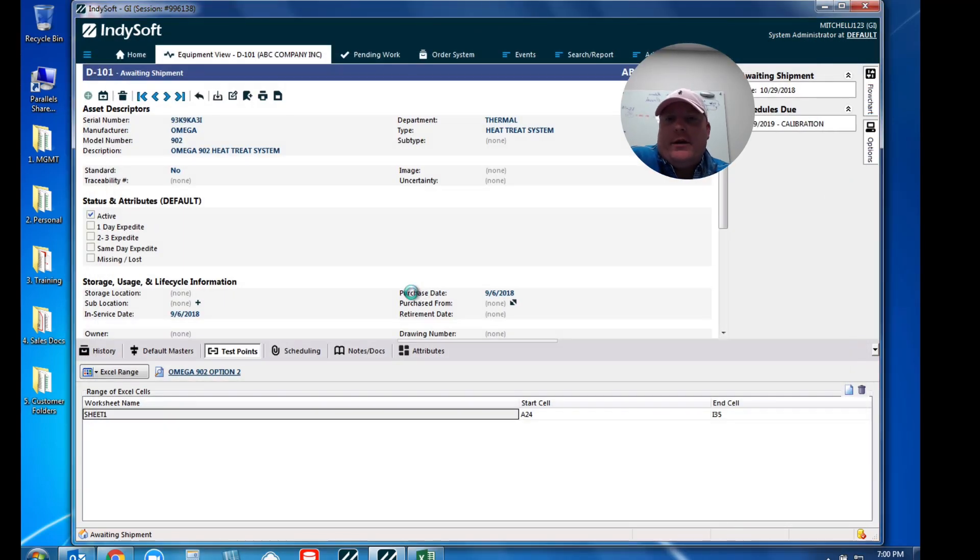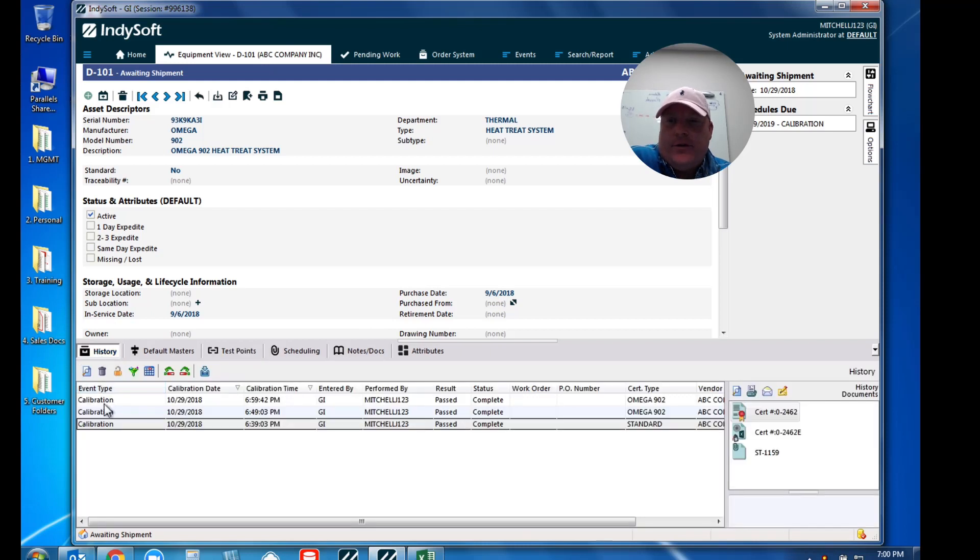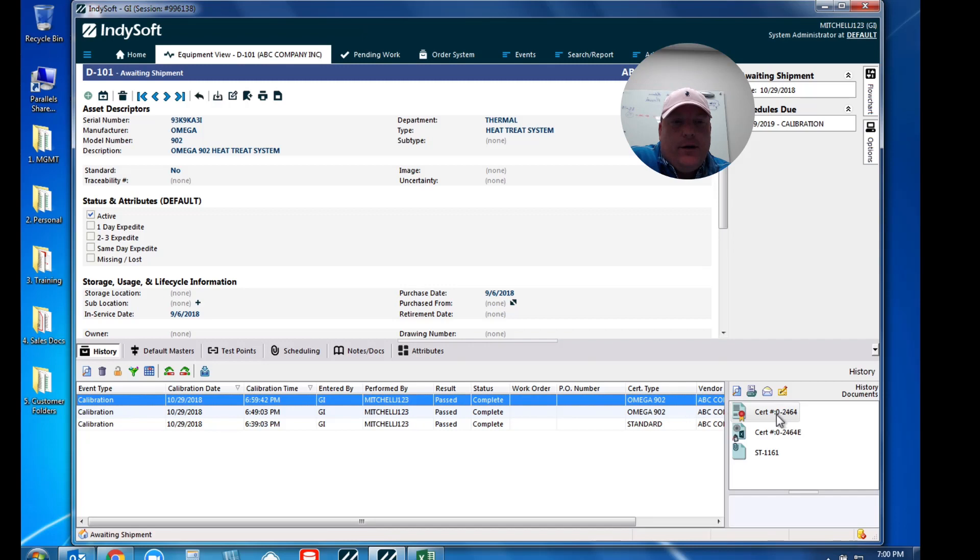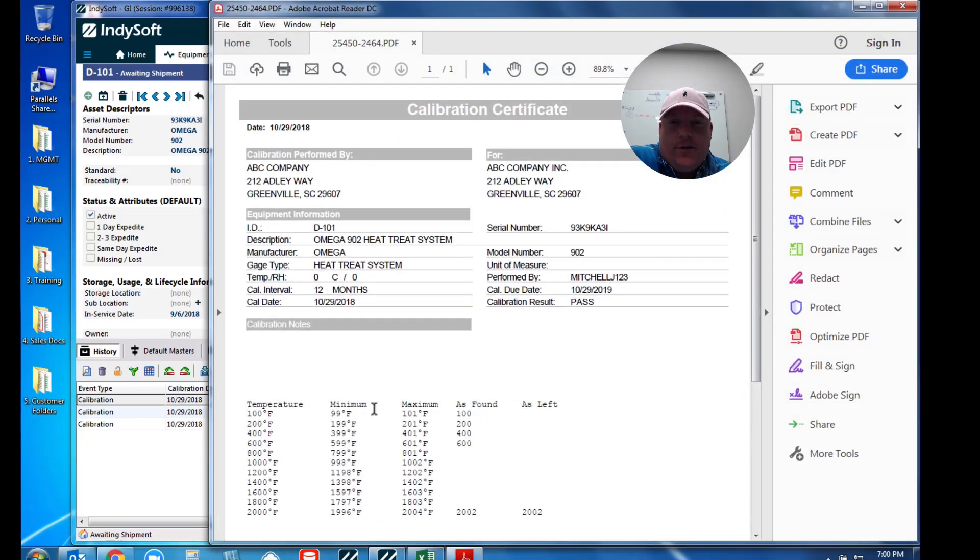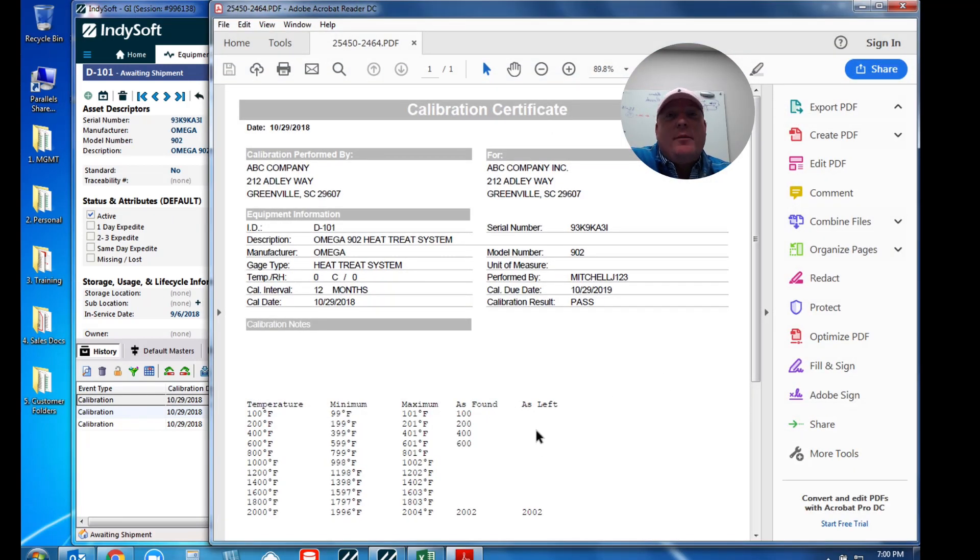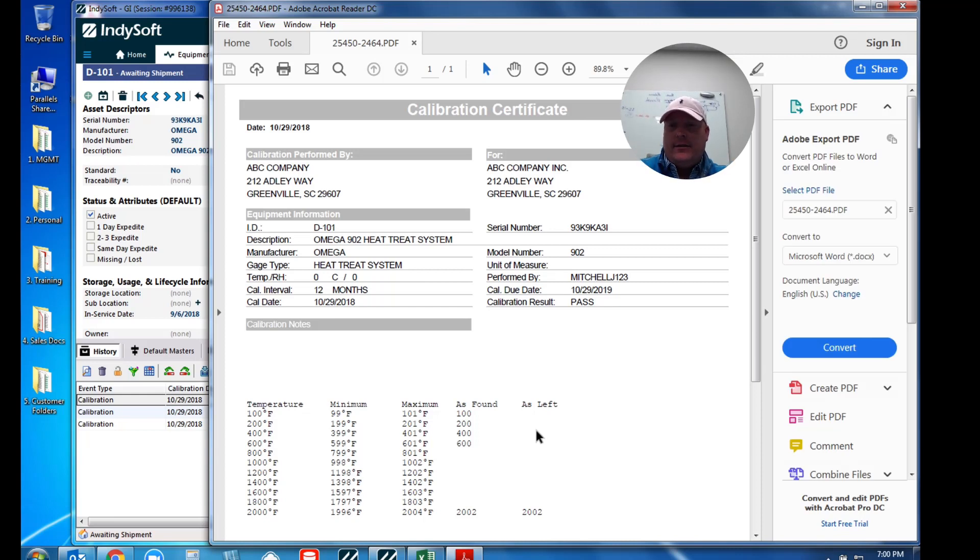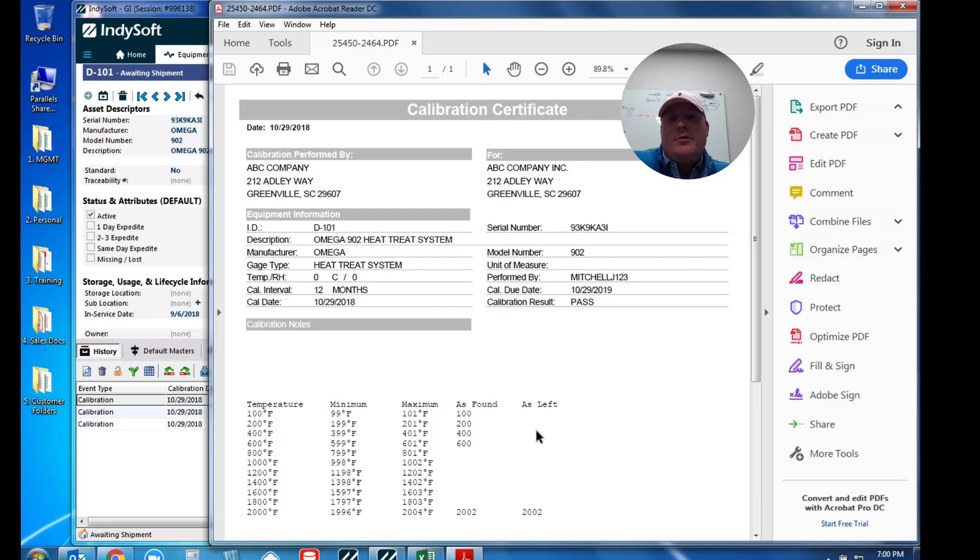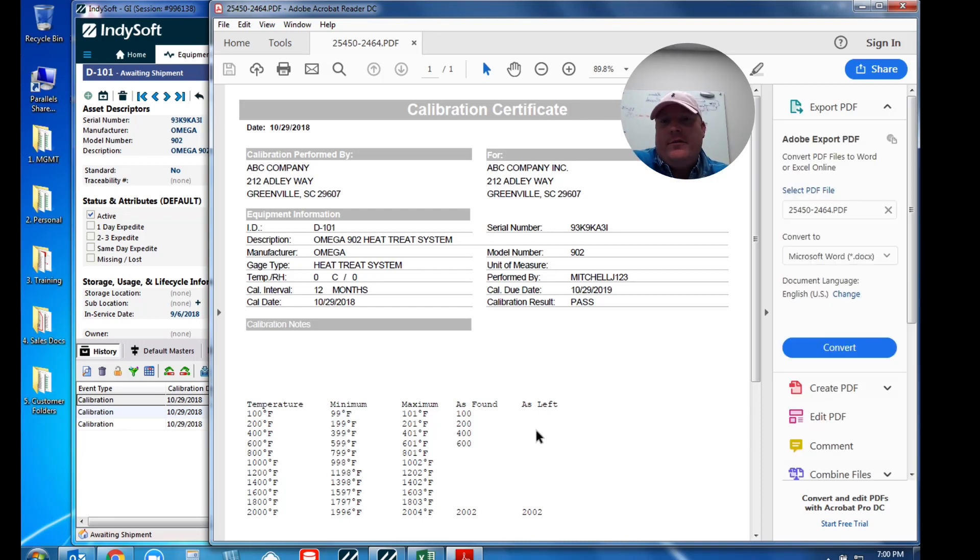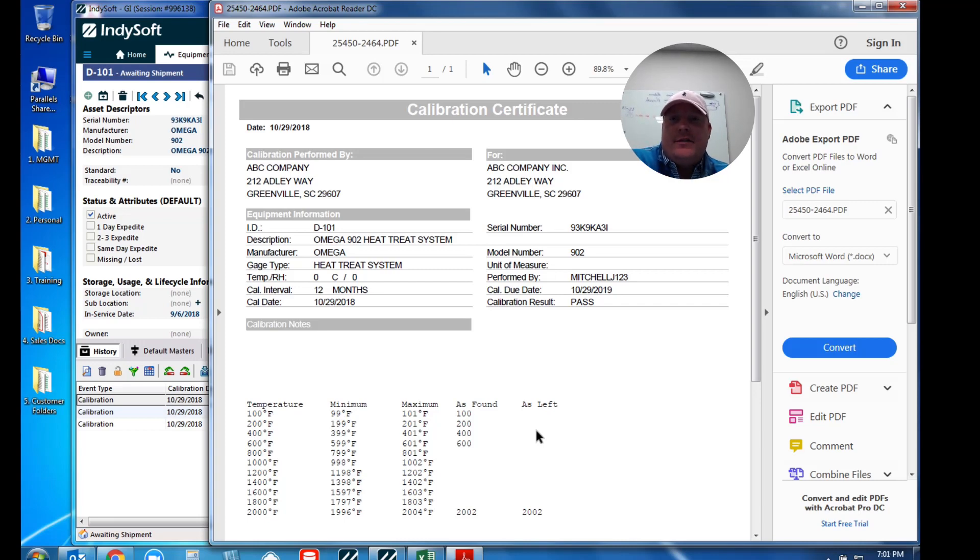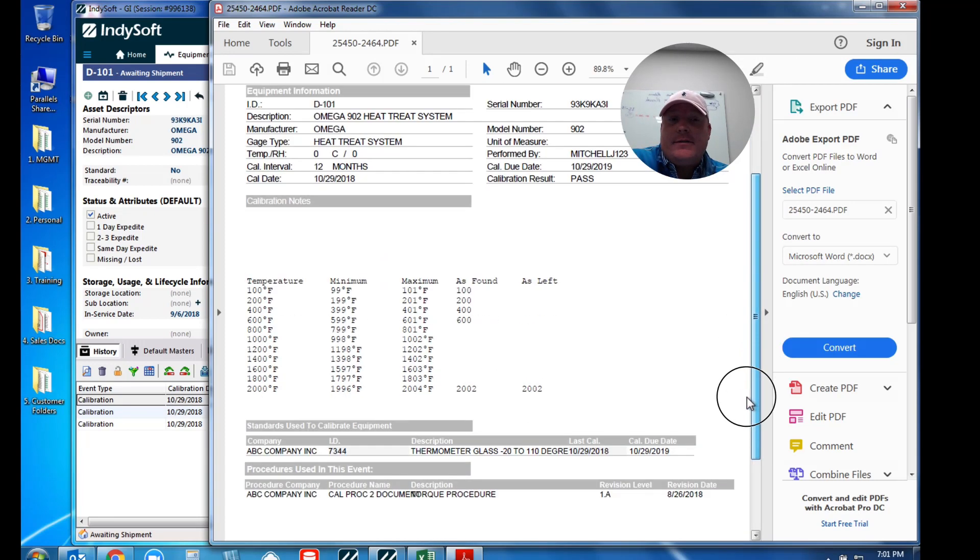But when we complete that, mark that as saved, and I have my copy down below open as well. When I mark that as finished, what we're going to see is in the history grid, when we print and generate those certificates, here's the one we just performed. If I open that up, what we're going to see is there's those exact data points, and you can even see the gaps on the ones that I did not fill out. So last week I got asked once or twice about how to perform the Excel embedding option. I hope this video gets you down the right path of getting that going. If you have any equipment where your data points are just in Excel and you want those to be embedded within to your existing IndySoft generated calibration certificates.